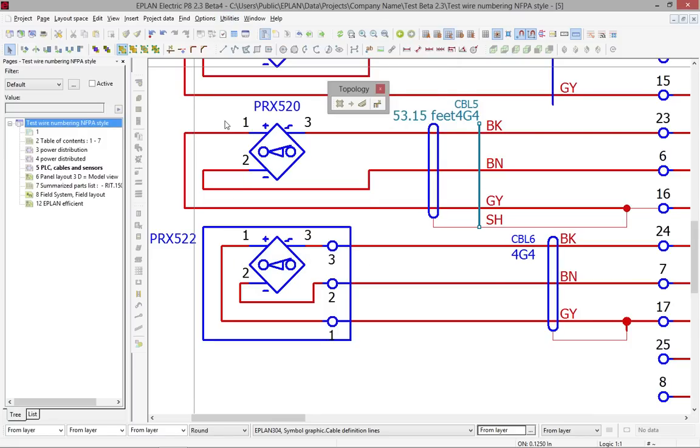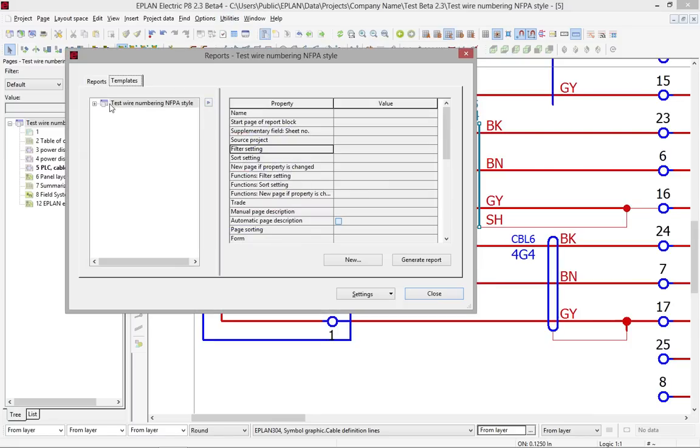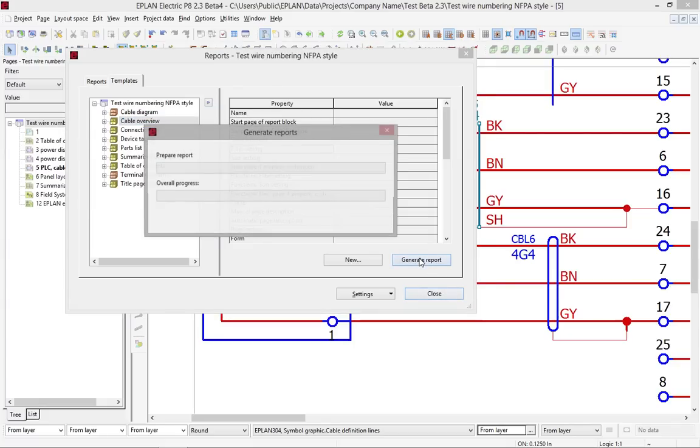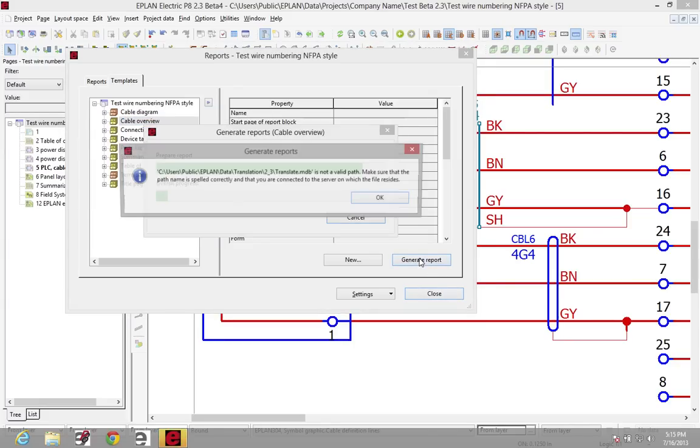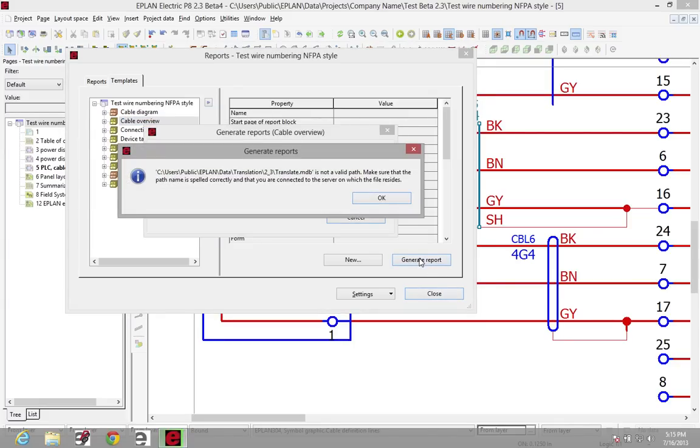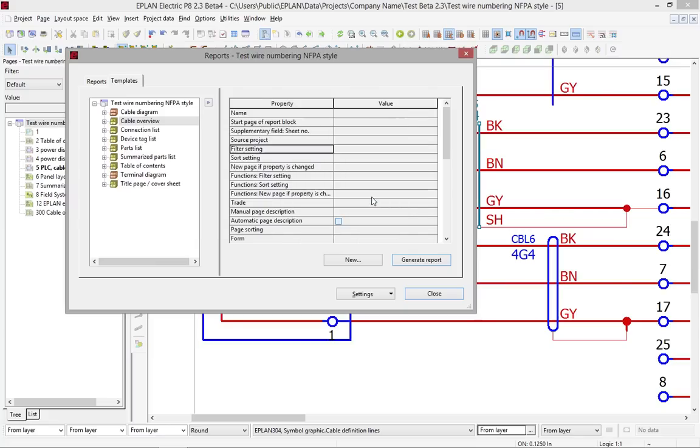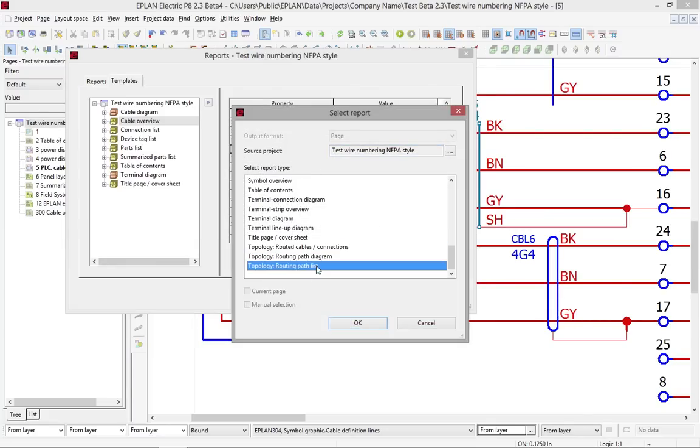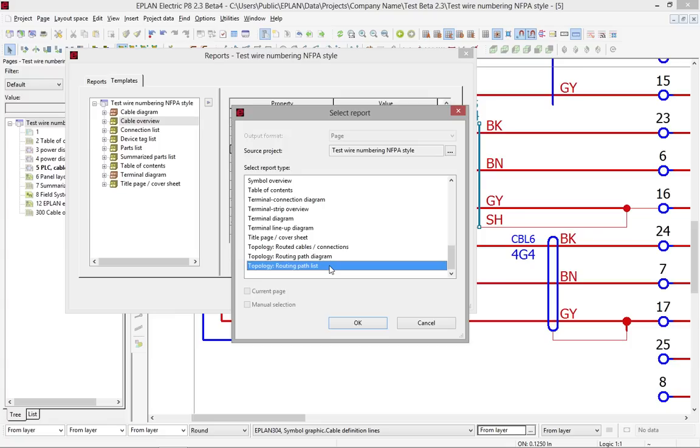If you generate, for instance here, a cable overview, the cable overview will tell you exactly what the length is for each of these components. The other thing that is also interesting is the fact that you can generate three new types of reports: topology routed cables, topology routed path diagrams, and topology routing path list. One is a build material that tells you what material has to be used. The other one is actually a pull list to tell you exactly from this box to this box in this tray, I will have these and these wires or these and these cables.